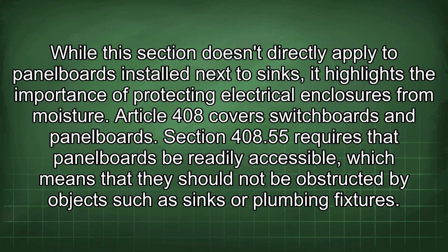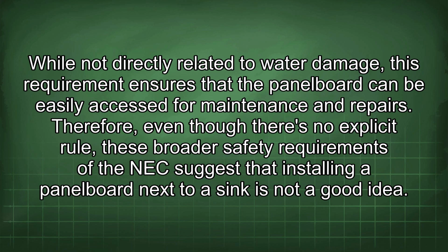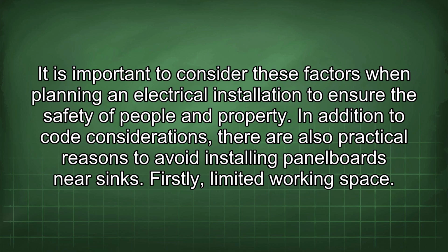Section 408.55 requires that panel boards be readily accessible, which means that they should not be obstructed by objects such as sinks or plumbing fixtures. While not directly related to water damage, this requirement ensures that the panel board can be easily accessed for maintenance and repairs. Therefore, even though there's no explicit rule, these broader safety requirements of the NEC suggest that installing a panel board next to a sink is not a good idea. It is important to consider these factors when planning an electrical installation to ensure the safety of people and property.